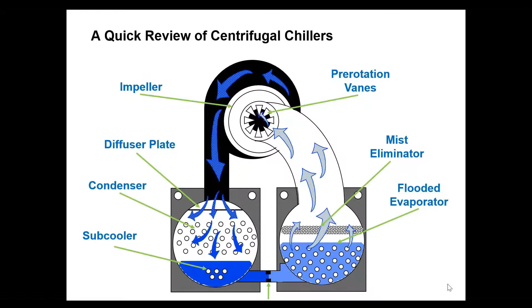This is typically a refrigeration cycle for a centrifugal chiller. You could probably see some animation on the right of your screen. This is the centrifugal chiller. The cooler that I had shown you in the previous slide is at the bottom. Here the refrigerant is moving into the compressor and getting pumped in the compressor and thrown into the condenser. The blue color denotes the cooler and the one on the top is the condenser. So it is getting thrown into the condenser, it is getting condensed, and it is again coming back to the cooler through a float valve, an orifice, or an expansion valve.